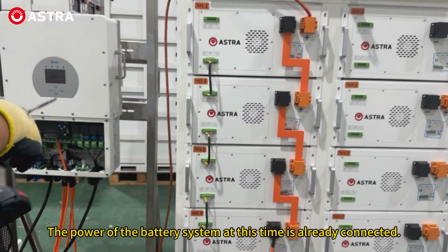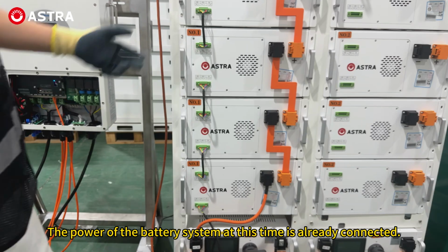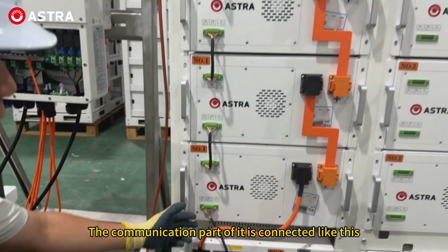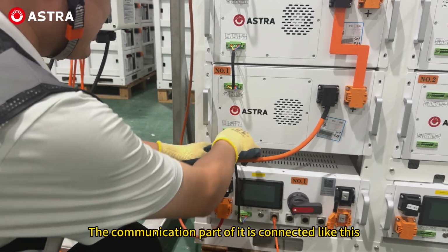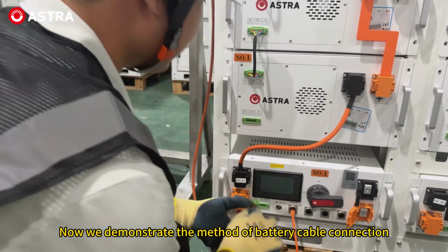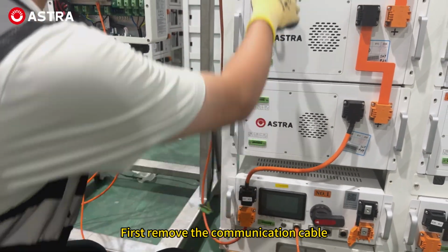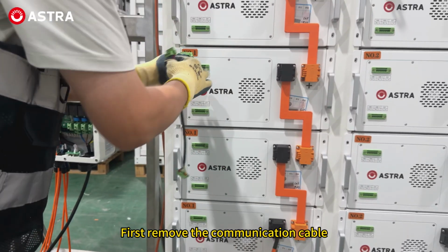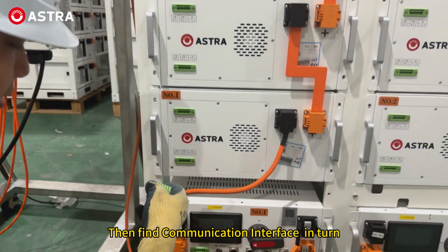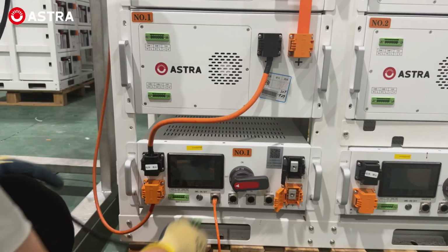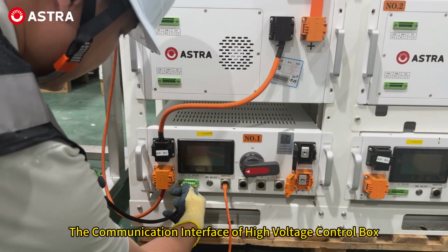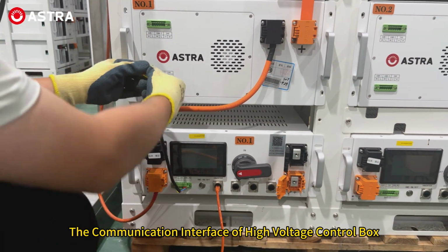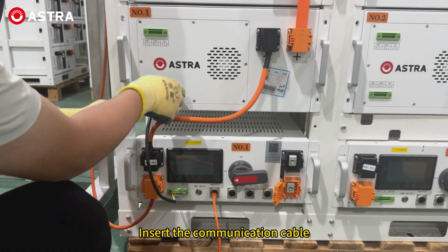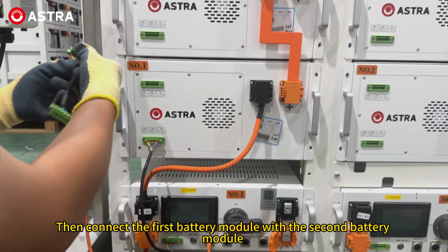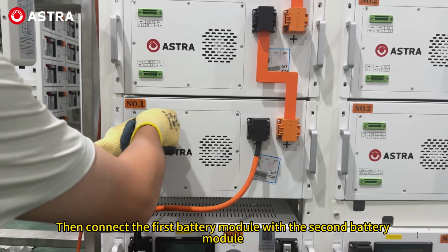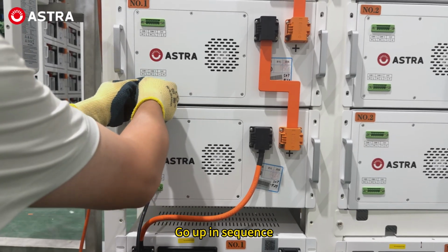The power of the battery system at this time is already connected. The communication part of it is connected like this. Now we demonstrate the method of battery cable connection. First, remove the communication cable. Then find the communication interface in turn, the communication interface of the high voltage control box. Insert the communication cable. Then connect the first battery module with the second battery module. Go up in sequence.